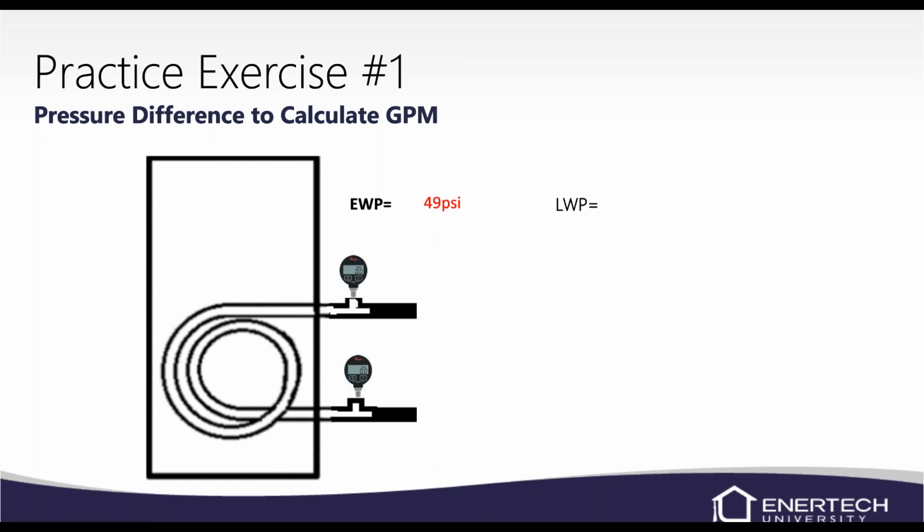So entering water pressure of 49 and we're leaving at 46. So that's pretty easy to do the math on that. We have a three pound pressure drop. That's not GPM, that's just pressure drop.